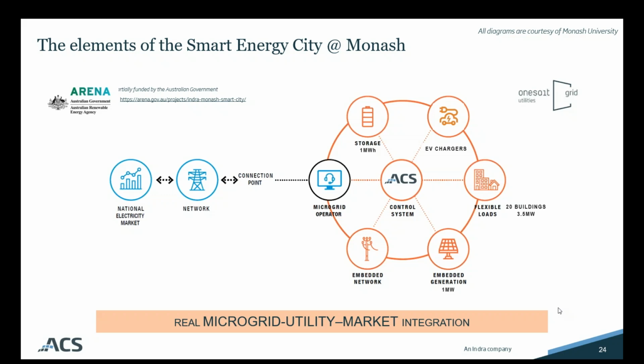The nodes can also trigger events on their own, for example, requesting the centralized platform to do a coordinated action. Typically, SCADA and DMS would monitor only feeders and at substation level, and not monitor many of the assets connected to them. So to extend the reach of traditional systems and to make this solution scalable, the use of IoT becomes essential. And that's why we basically chose this configuration.